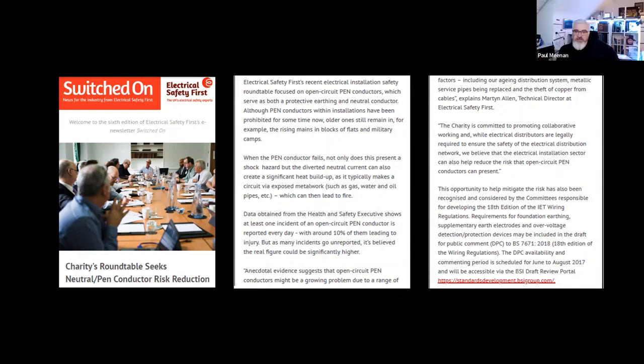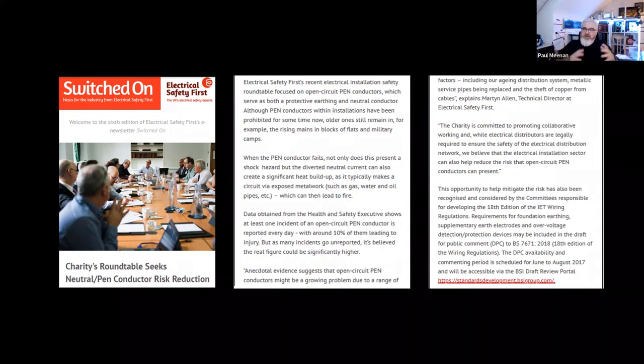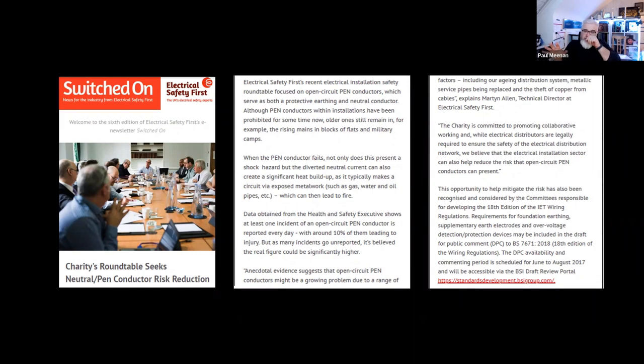The interesting bit, Dave, is that phrase 'legally required to ensure the safety of the electrical distribution network.' In the Western region, when electricians ring 105 and say they've got a lost earth, the DNO says just stick a rod in, it's not my problem, even when that installation had been supplied by an earth for decades. So I think there are some poor behaviours in the industry now, maybe due to volumes and how they repair it, but a lot of it's getting thrown onto the consumer rather than being treated as the legal obligation of the network. That's not a dig at any one DNO, it's an observation from speaking to hundreds and hundreds of electricians.